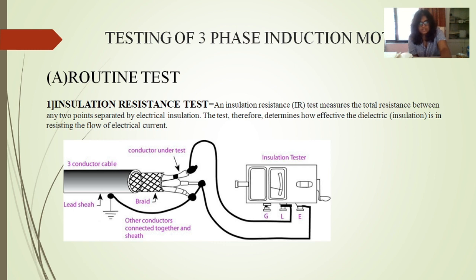An insulation resistance test, that is IR, measures the total resistance between any two points separated by the electrical insulation. The test therefore determines how effective the dielectric, that is the insulation, is in resisting the flow of electrical current. As you can see in the diagram, there is an insulation tester, and the tester is connected to the conductor, and the other is connected to the lead sheath.